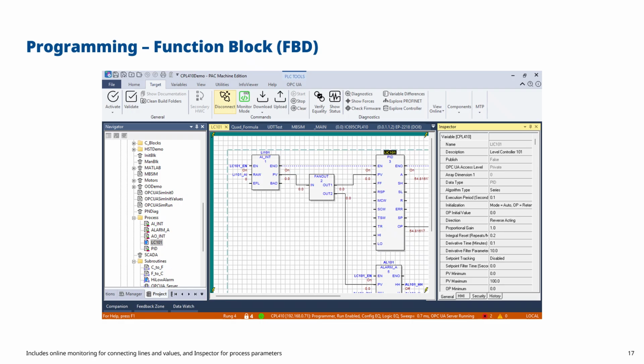I've got a fan out. This is used to have a single input with multiple outputs. This one doesn't have any instance, so it's just a simple function block. But then I've got my PID controller, LC101. And then I've got an alarm block as well, AL101, and you can't see it, but on the right hand side I've got my output to the actual analog output integer block, which is my actual analog output valve.